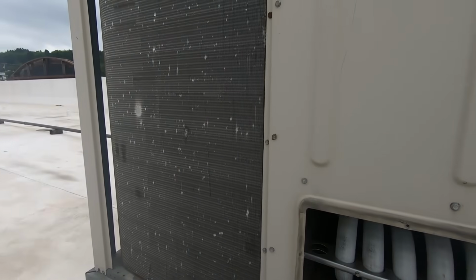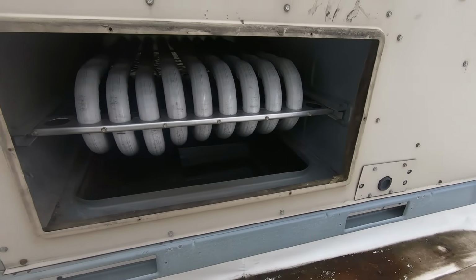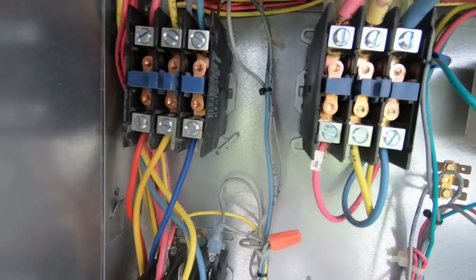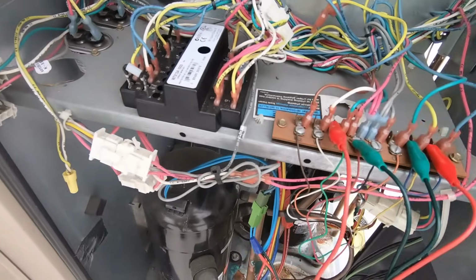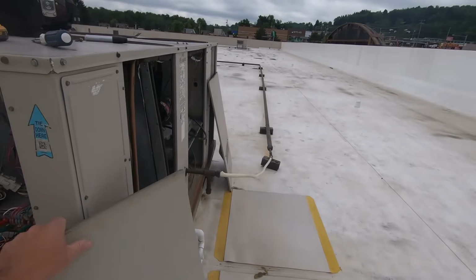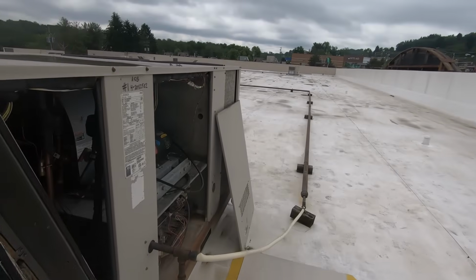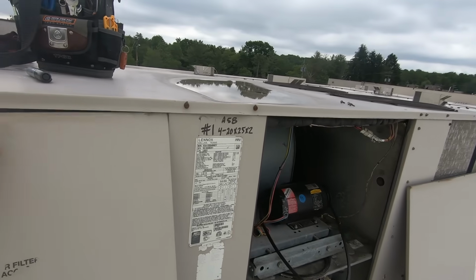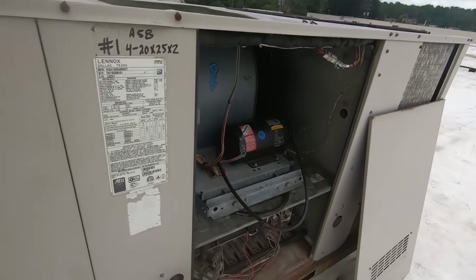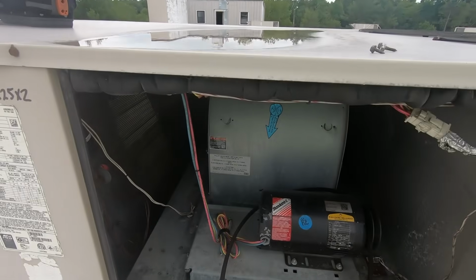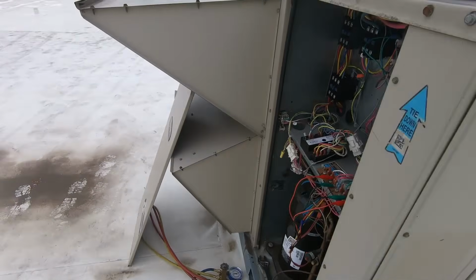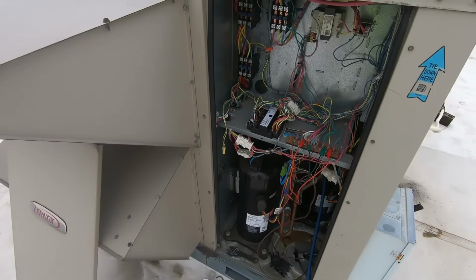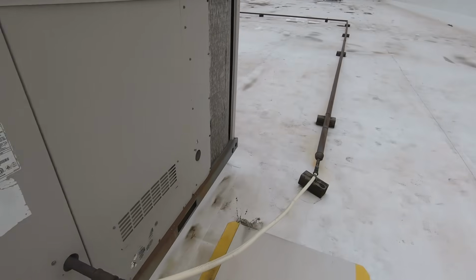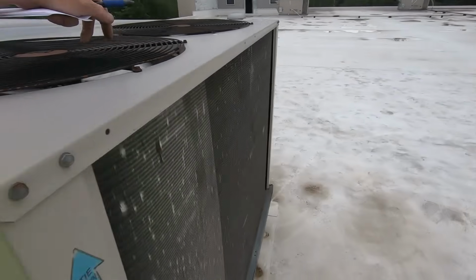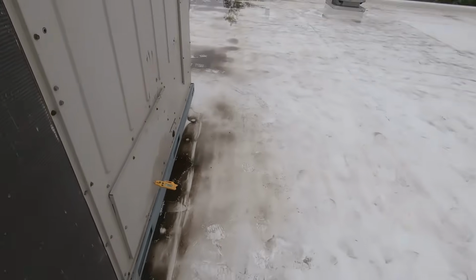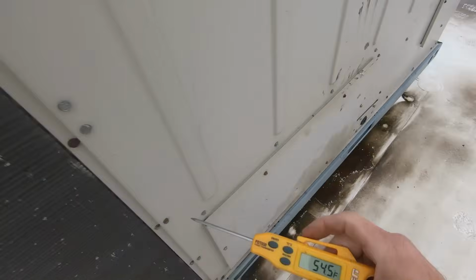Check these coils, check these condenser fan motors, the electrical, and then we'll run it in AC. Contactors all look good. Got everything jumped out, Y1, Y2. Let's put some panels back on, clear this drain trap, see what kind of supply temp we're getting, and hopefully we can just buzz right through these. All right, drain trap's cracked. Both stages are running, both fans are running. Needs a new belt, needs filters, gonna clean coils, putting out 54-degree air.